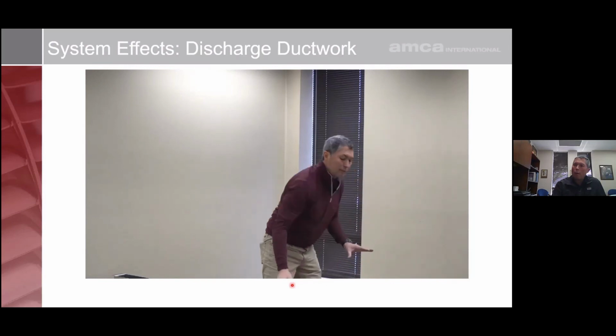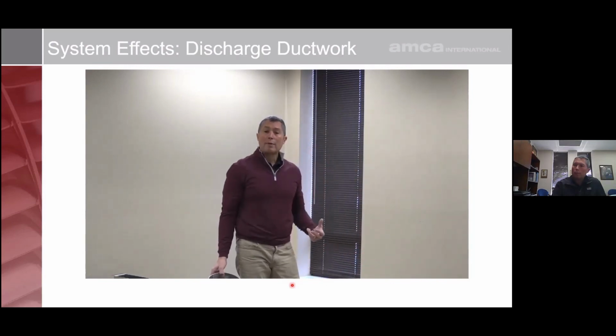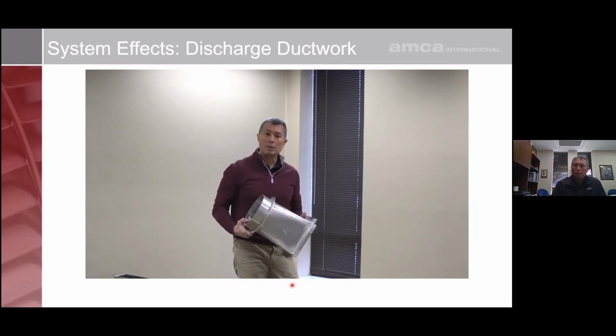Now when you have a straight run of ductwork, you want to have the proper length, which is typically 3 duct diameters for the first 3,000 feet per minute in velocity, and an additional duct diameter for each additional 1,000 feet per minute in velocity. However, it's better to have something rather than nothing. So if you're space constrained, it's good to have a short piece of ductwork rather than no piece of ductwork.